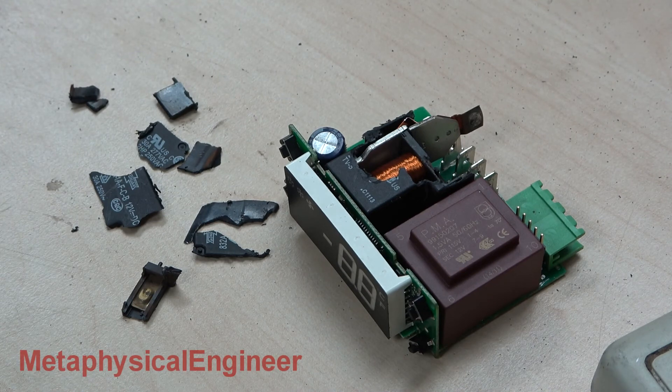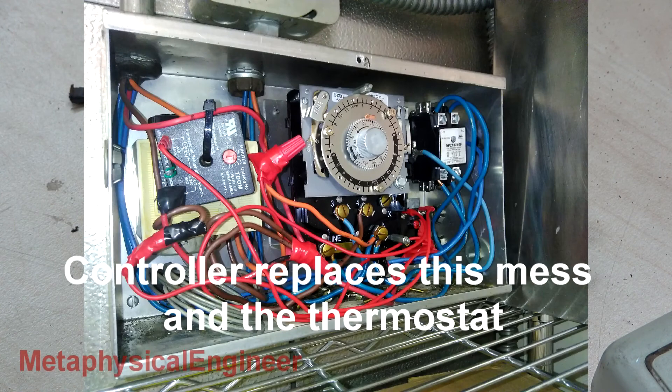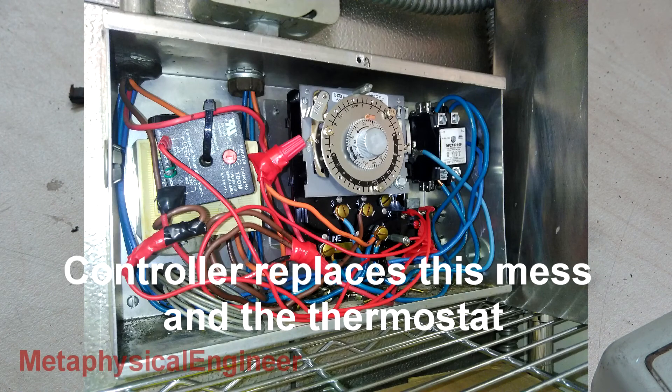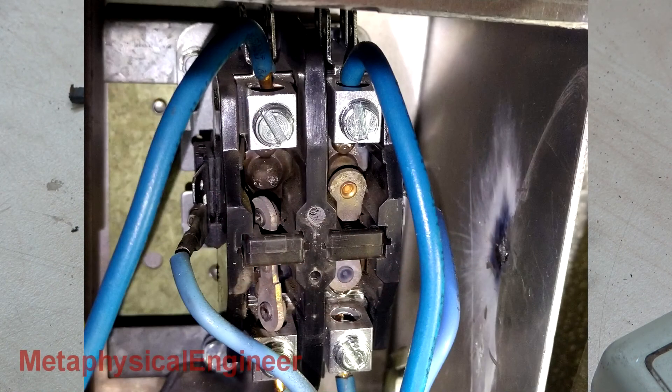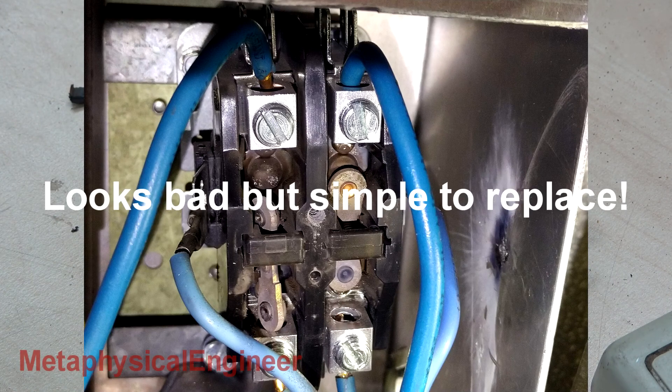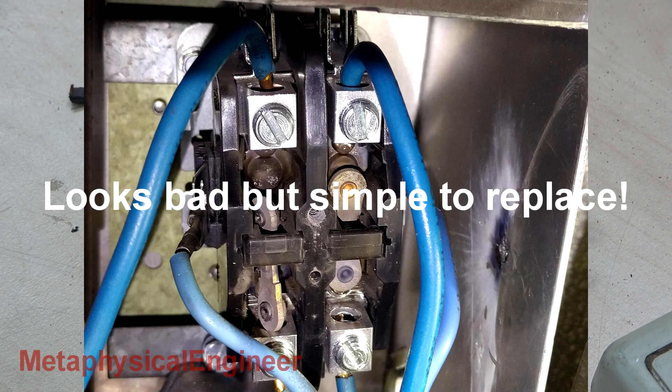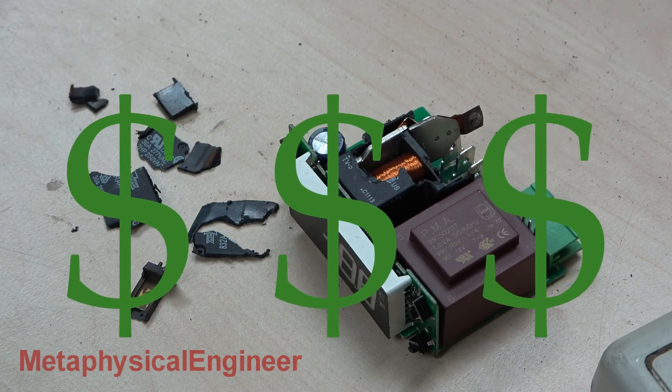These things are everywhere, and it's a shame cheap parts let them down, as they otherwise need far less maintenance than mechanical temp controls and defrost timers. Where allowed, I like to see these driving a contactor instead, which gives greatly extended life, and is far cheaper to replace considering these controllers can approach 200 bucks each, wholesale cost.